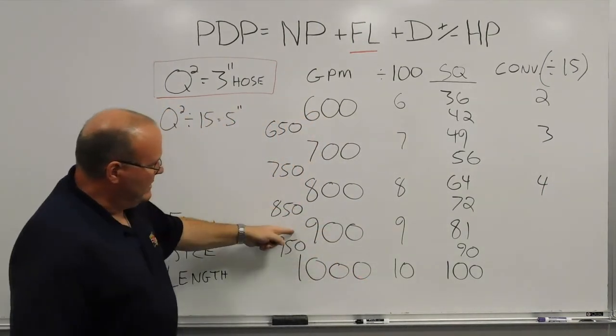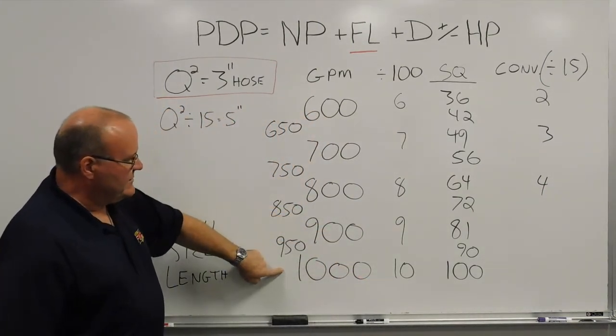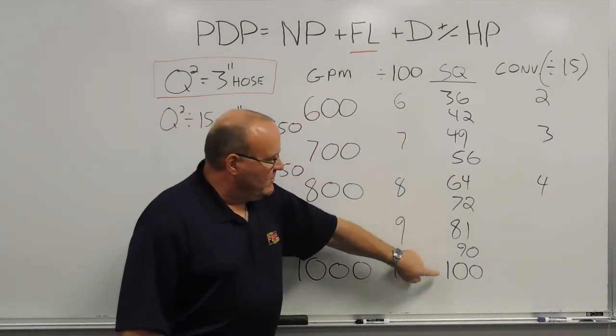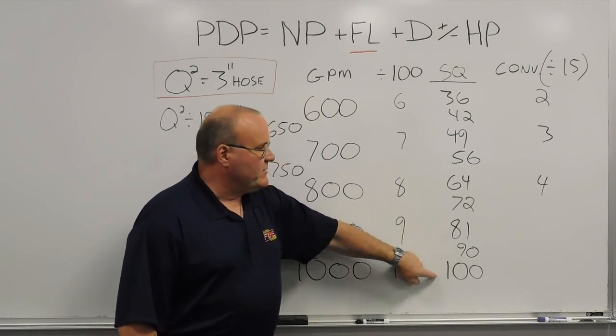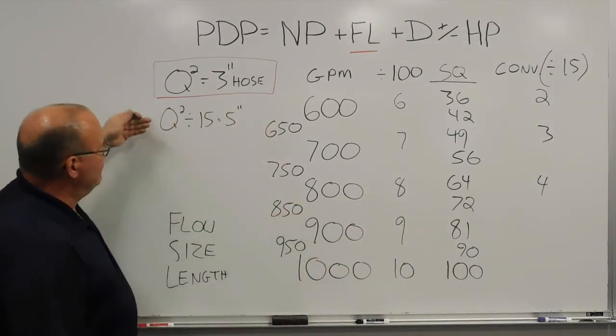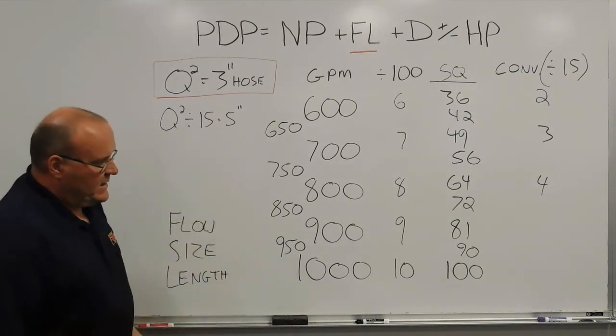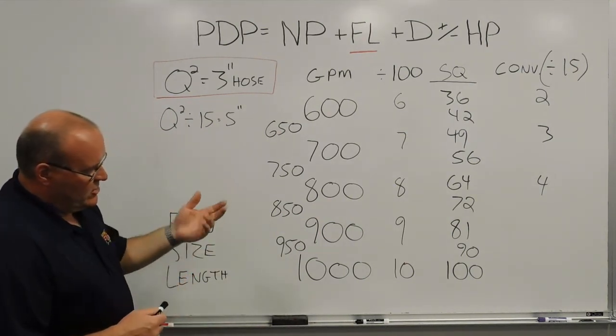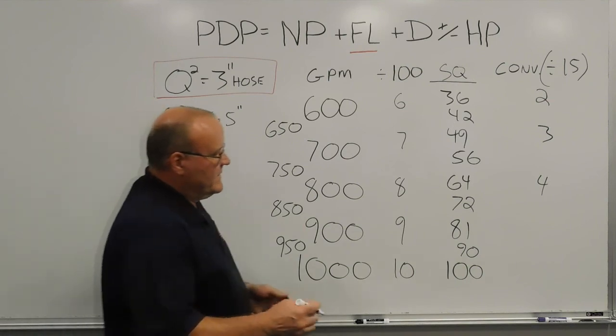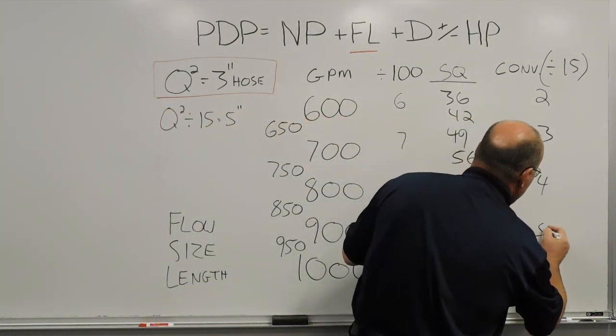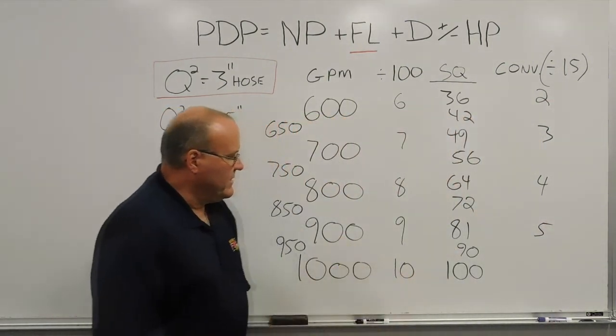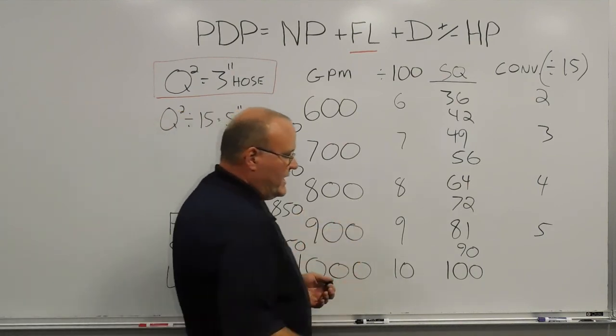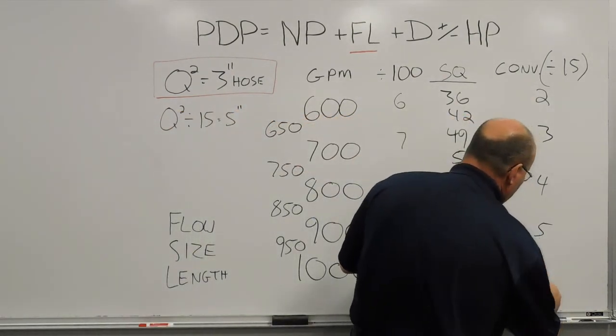And then working right on down the line, 900 and 1,000 gallons a minute, 81 and 100 respectively are your 3 inch hose friction loss numbers. So 81 divided by 15, you're going to end up with just over 5. And then for 100, you're going to end up with almost 7. So 6 and change. We'll just call it 7.